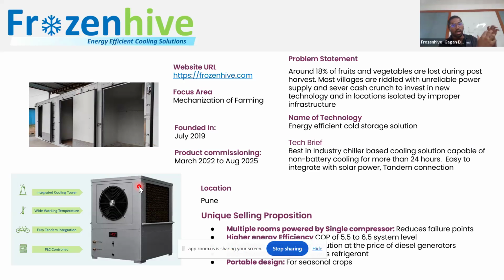This new ambient temperature becomes the heat rejection temperature for the next cooling stage, done by the chiller system, which is again a vapor compressor kind of system. This architecture gives a phenomenal COP—the efficiency is around 6 COP.